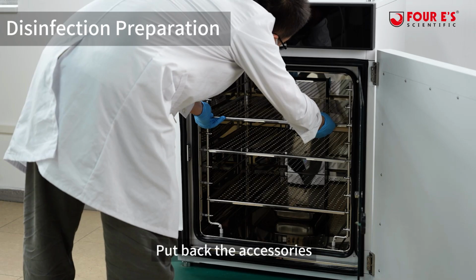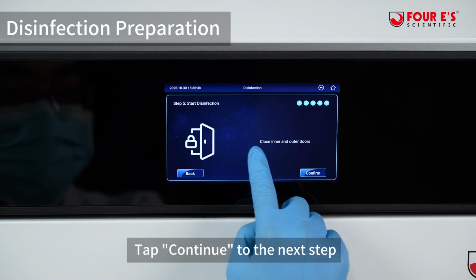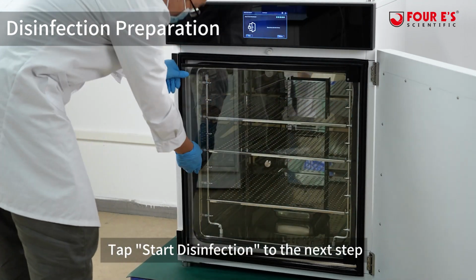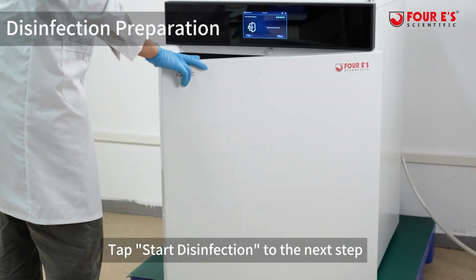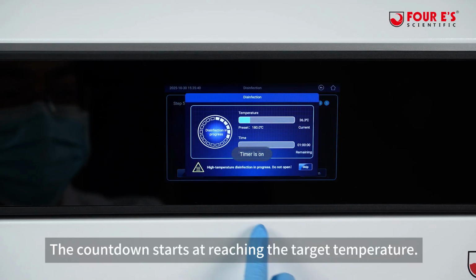Put back the accessories except for the HEPA filter module, then put back the clean stands and drip tray. Tap Continue to the next step, then close all the doors and tap Start Disinfection to start disinfecting the incubator. This monitors real-time and preset temperatures. The countdown starts at reaching the target temperature.